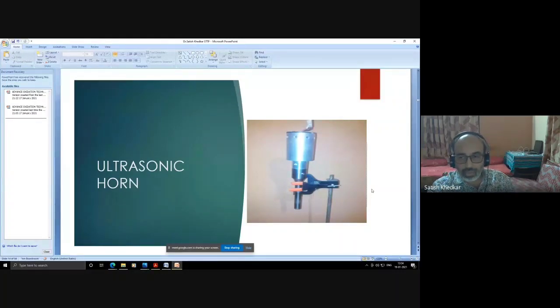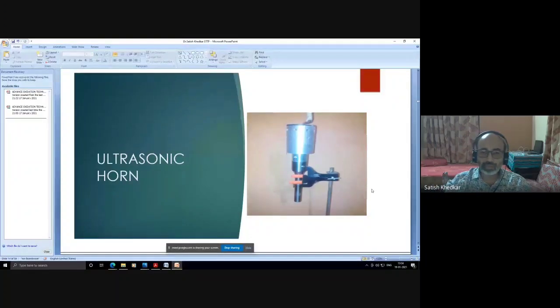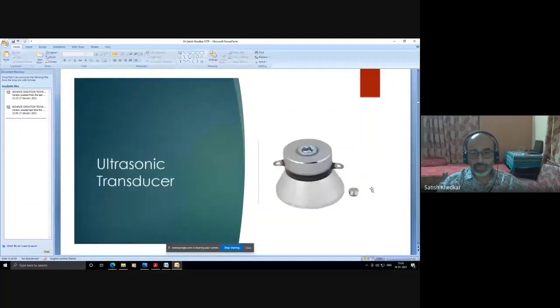Now how the transducer looks. Now this is the transducer, which is responsible for conversion of electrical energy into mechanical energy. Now the transducers are sensitive to load. That means you cannot put highly viscous liquids into the cavitation zone, where you are cavitating the sample, immediately adjoining the probe, because sometimes there is short circuiting of the transducer because of the load.